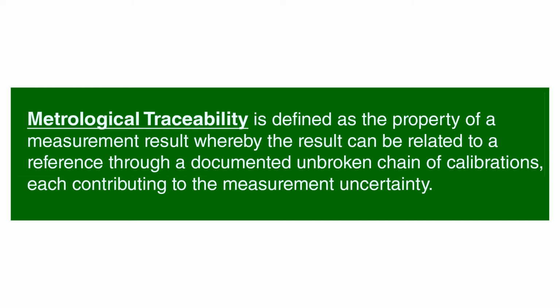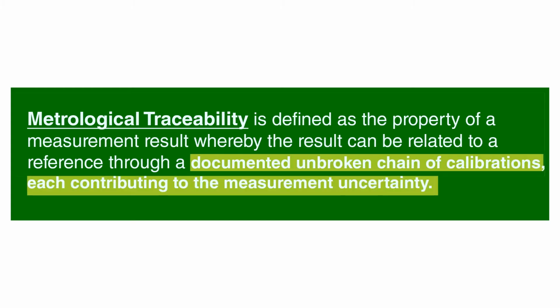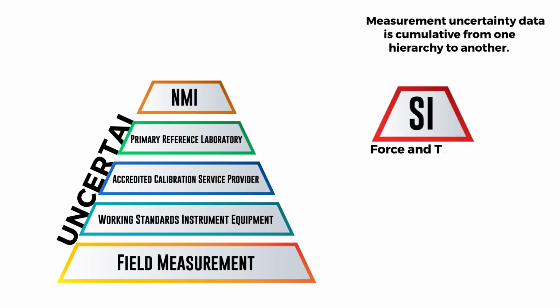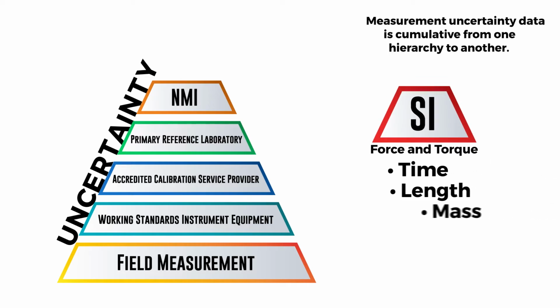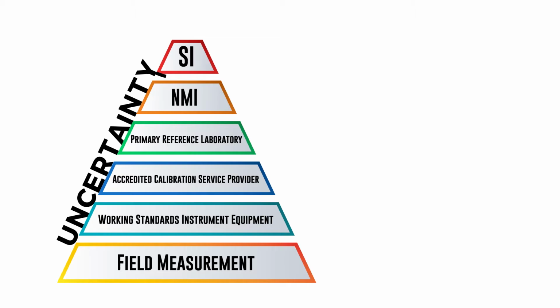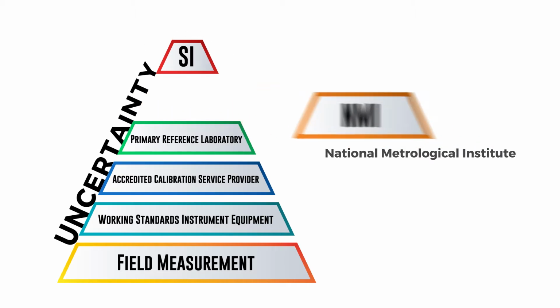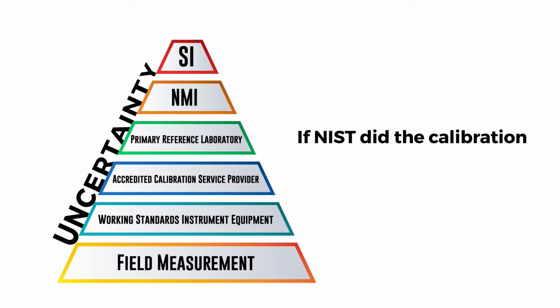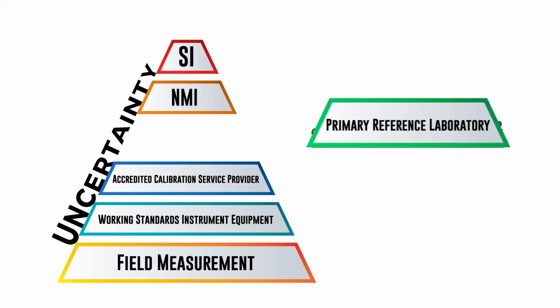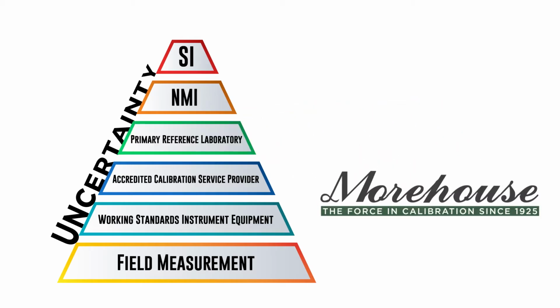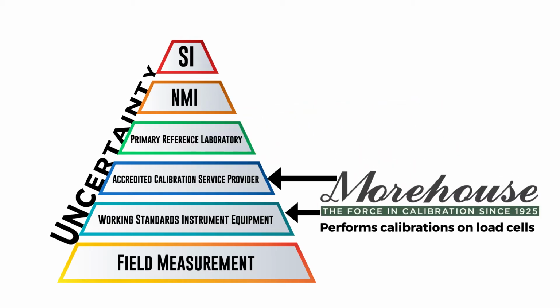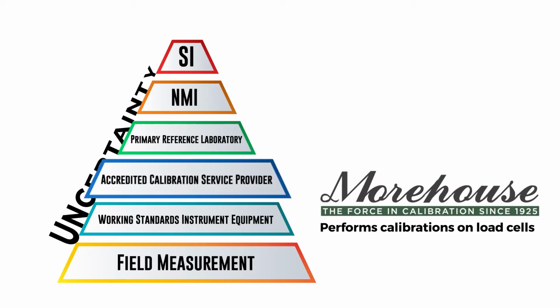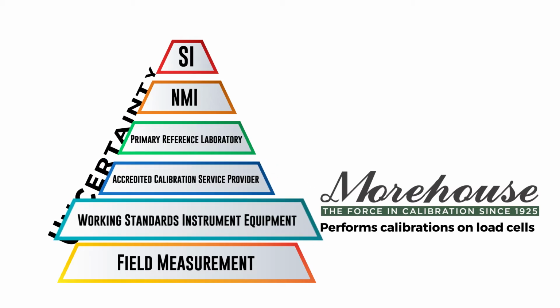Let's first define metrological traceability. That measurement traces back to the International System of Units, SI. For force and torque, these SI units are time, length, and mass. The pyramid starts with SI at the top, then NMI, National Metrological Institute, like NIST. If NIST did the calibration of the force weights, then the next tier would be a primary reference laboratory like Morehouse. Morehouse performs calibrations on load cells for the lower tiers, accredited calibration suppliers, followed by working standards, who in turn calibrate field equipment.